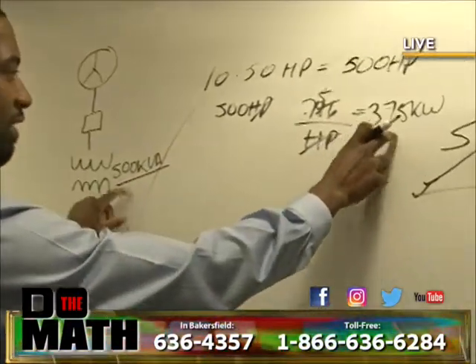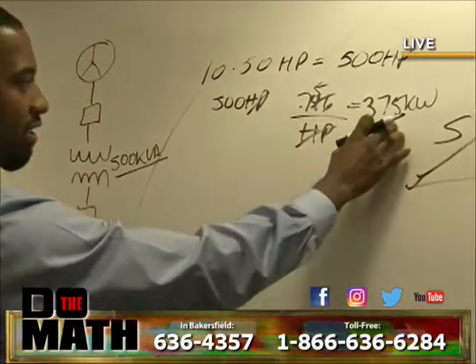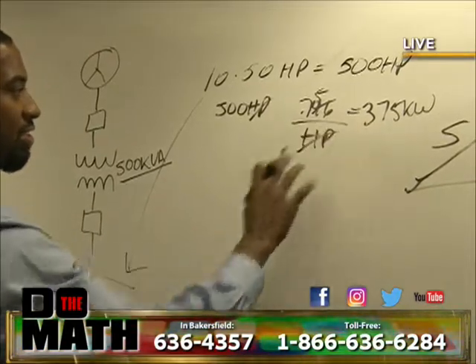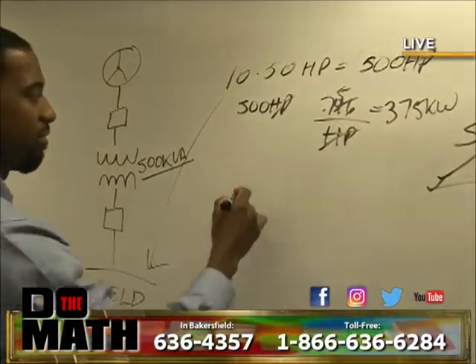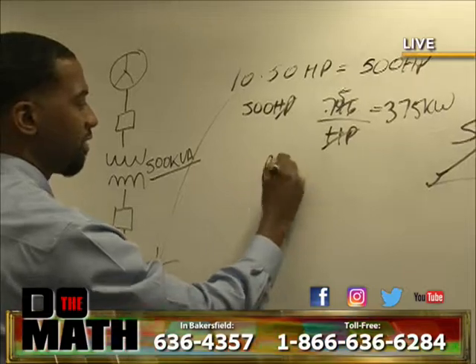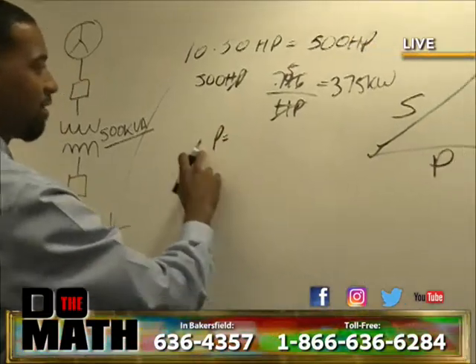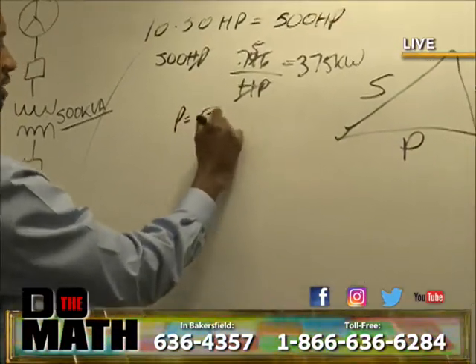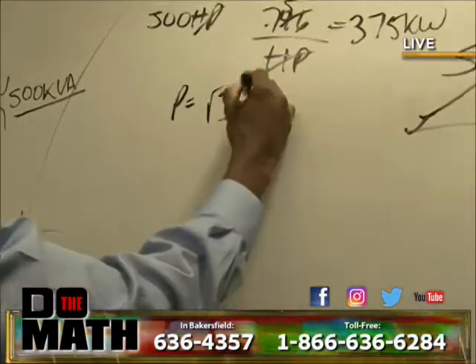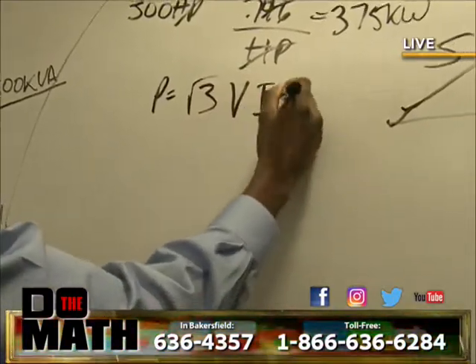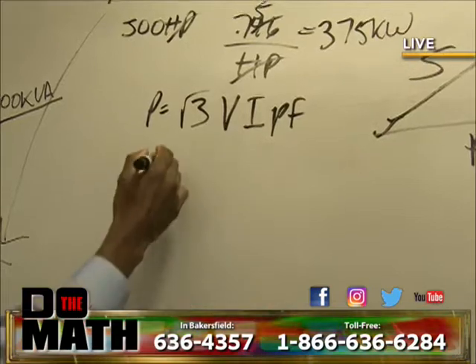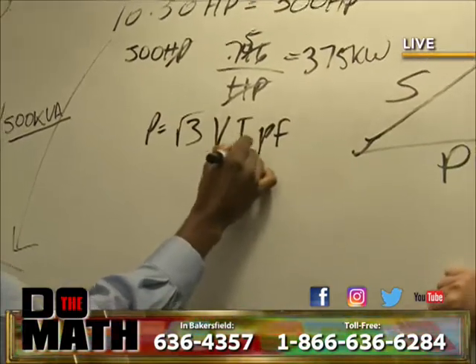So I mentioned we wanted to get similar units. We're still at KVA, we're still at kilowatts. I need to get this in amps so I can compare the capacity of the transformer. So I'm going to use the power equation P, that's my real power in units of watts, equal to square root of 3, because it's three-phase power, times volts, times current, times our power factor. And we're going to solve for I, which is amps.